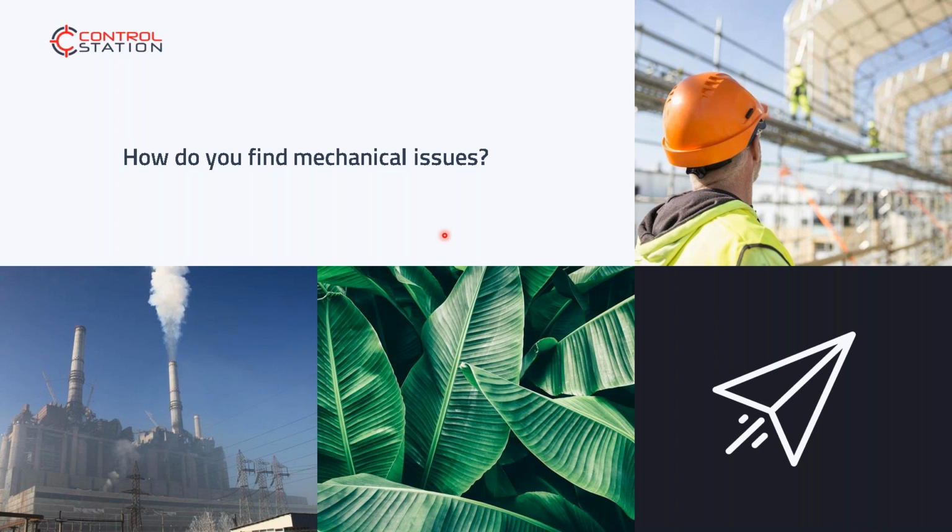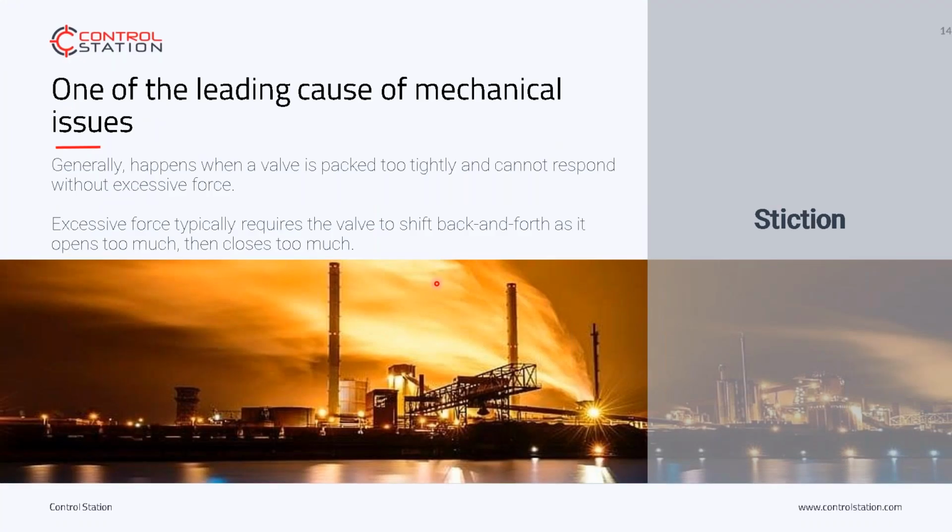What has changed? Have we worked the valve too hard? Is there a quality issue within the valve components? Is there a maintenance issue? All of which can be related to those mechanical issues that have caused our poor performance, or caused you to be standing in front of a process at hopefully some reasonable hour in the day, but potentially can pull you in operationally at different times.